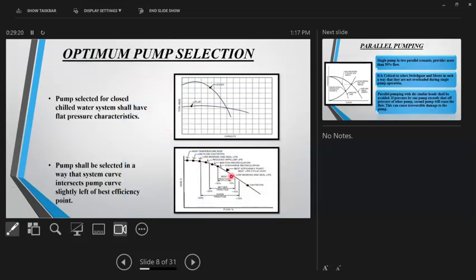Yeah, I'll go back to this. You're talking about, let's say, for a particular pump manufacturer, you don't get a selection within this zone, correct? Yes. Usually this doesn't happen. This can happen when your operating point is very skewed, for example, very low flow and very high head. If you have something of that sort, then you may not get a selection in this best practice zone.